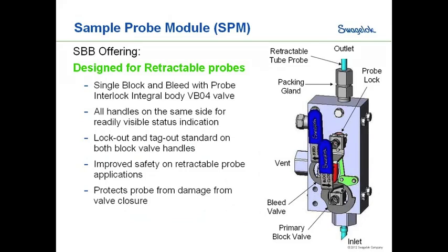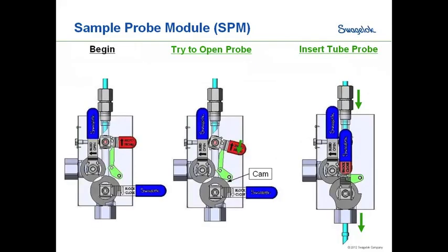For retractable probes, one of the longstanding problems has been operators closing the isolation valve with the probe still inserted, which can crush the probe and make it difficult to remove. In our design, there's an extra probe lock valve, and everything is interlocked. The key interlock is that you cannot shut the process valve unless you have first withdrawn the probe — so you physically cannot crush it.